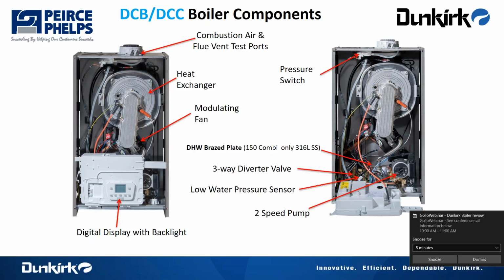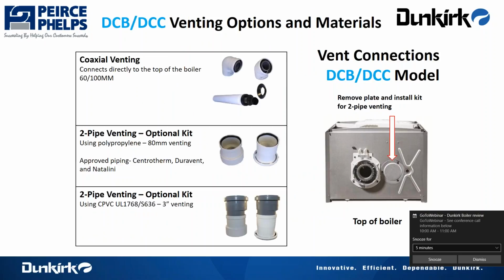Pressure switch on the unit, reading pressure across 2 different points. The braze plate where it sits down below the heat exchanger, the diverter valve and diverter hydro block that sits inside the boiler that we manufacture and test in Utica, and the 2-speed pump. Our venting options with the boiler, we have 3 venting options. Top option, probably the primary option, is the vent pipe that we have in stock here. It's a coaxial system, outside aluminized steel vent pipe with an inner pipe of polypropylene, with a starter elbow, termination kit, vent lengths, and 45s.